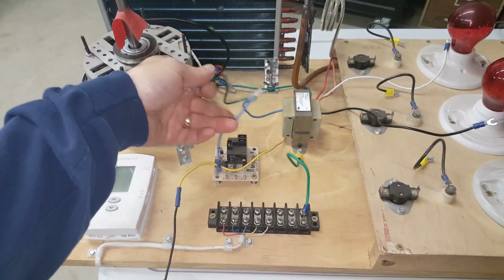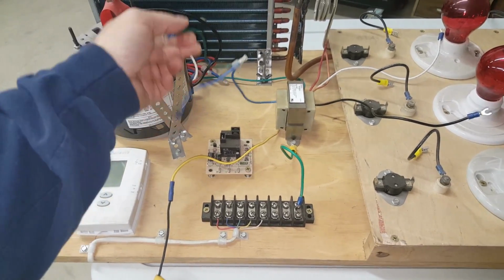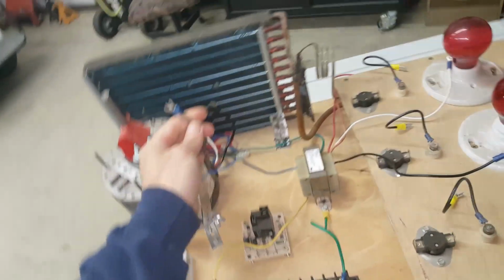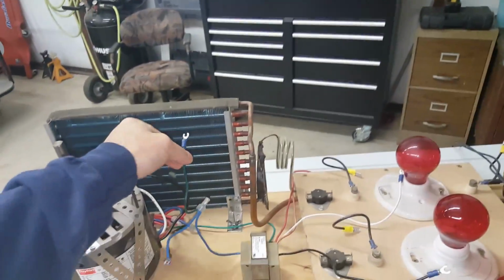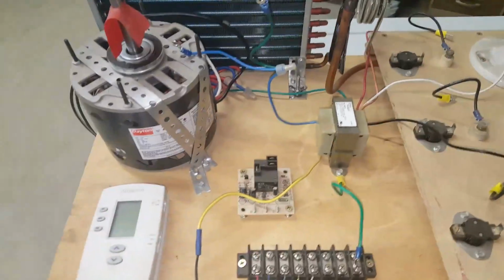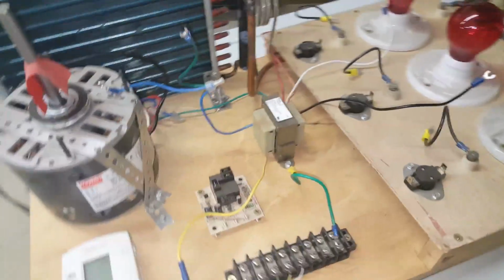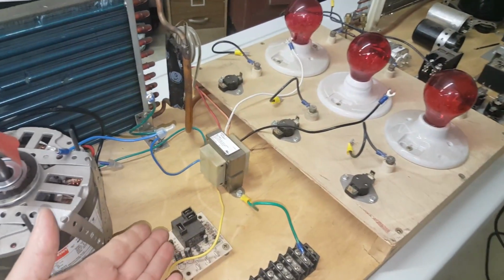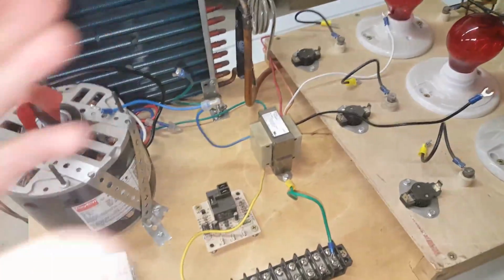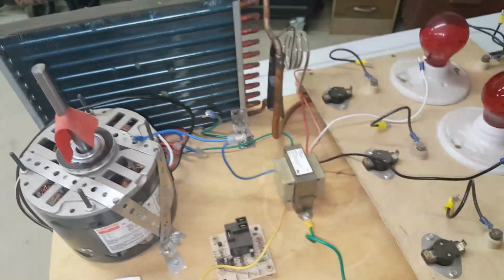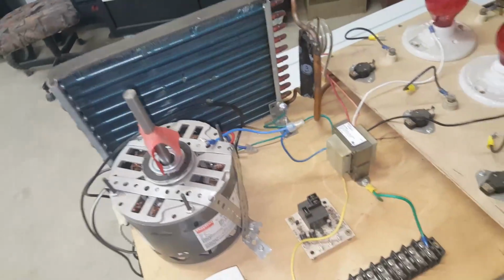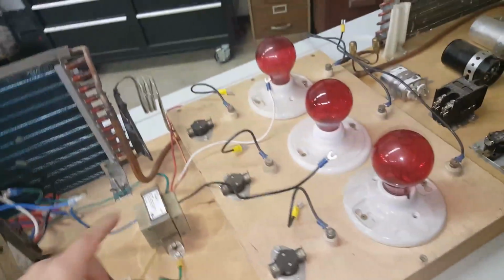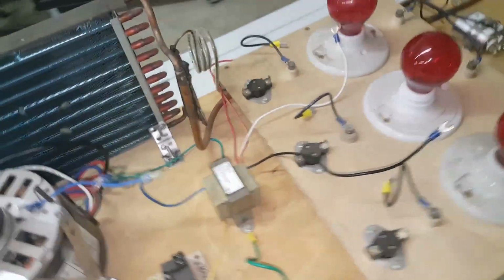It's a lot cheaper to replace the fuse than to replace the complete transformer. Then we'll have the common side of the 24 volts that goes to each individual 24 volt coil that we'll be talking about later, and it'll also be grounded to the chassis. We're going to talk a little bit about the transformer also. It's rated in the voltage of the primary side and the secondary side, but it's also rated in VA, which is volts times amps, which is watts. Same thing. If you hear VA, you might hear it called watts. This particular transformer is a 40 VA.